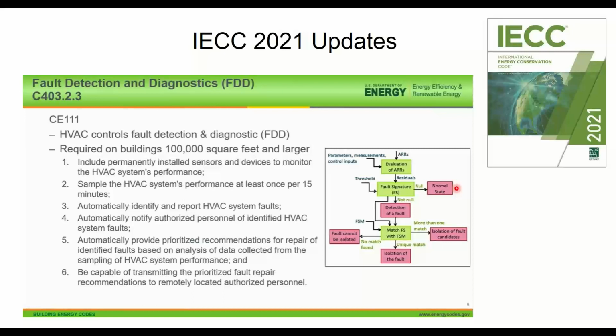And the reason we have that is because economizers are great and they save energy, but a lot of them fail and no one knows they fail because something else, i.e. the cooling system, eventually kicks on and makes up for the fact that the economizer damper is stuck, right? So it just gets kind of lost. So this is a way for it to be identified early on so we don't lose out on that energy savings. Well, that same idea, FDD, on economizers is now getting applied to the whole entire system.